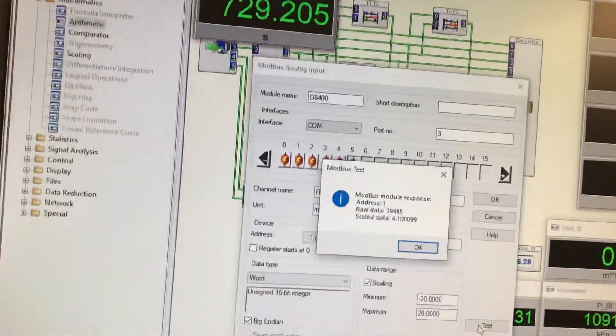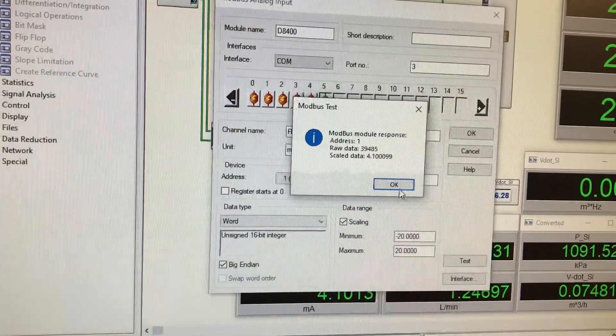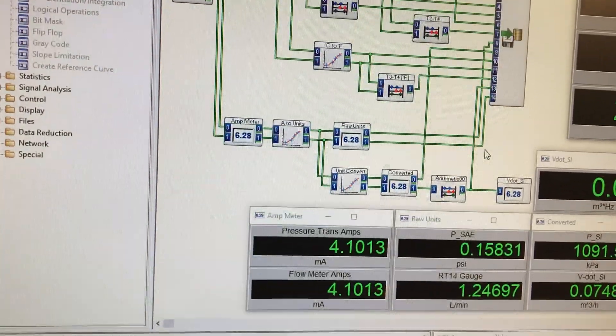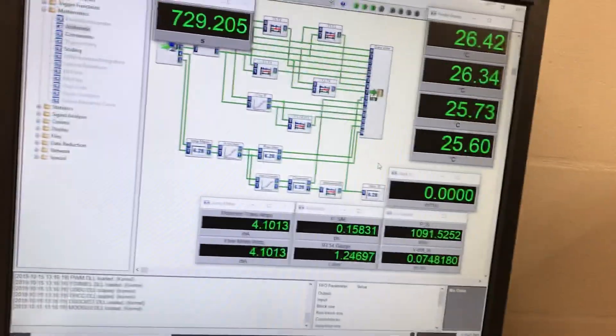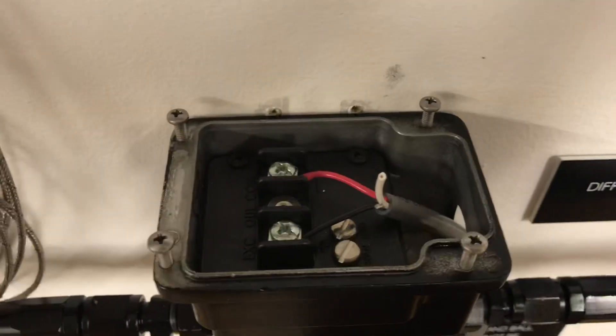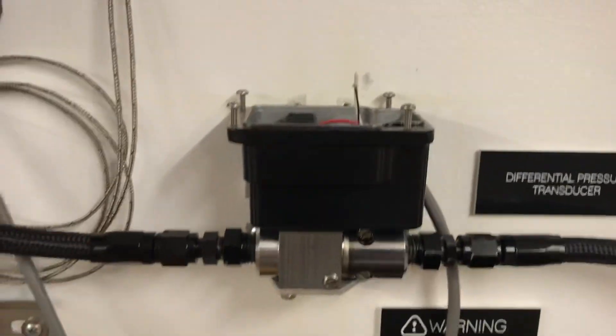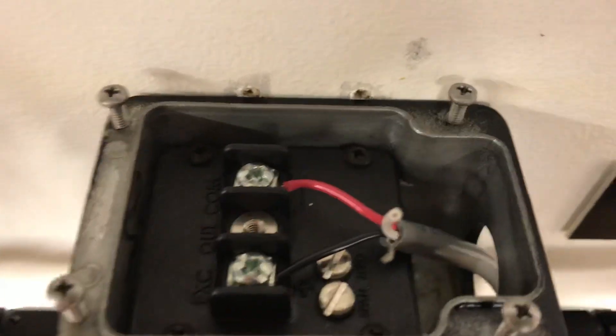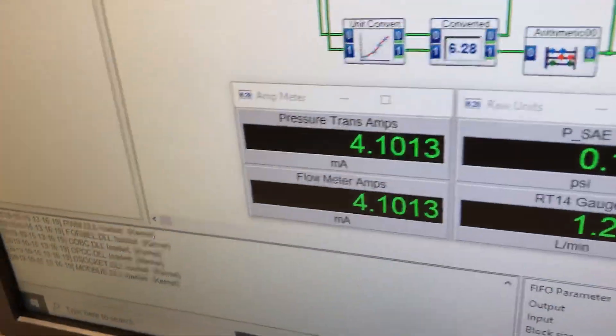You can see that when I test it, we're basically getting what is more or less normal. Now, asterisk here — when this system was first set up, I don't know what was messed with on the span and zero for this. But regardless, you can see that the ampere rating is more or less the same. That takes care of the DAC scaling and adjusting the units.